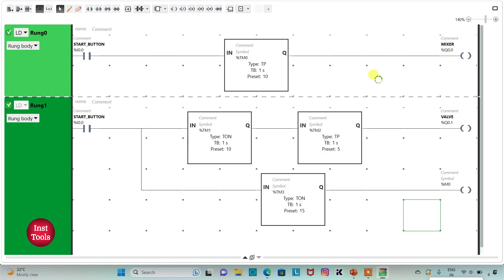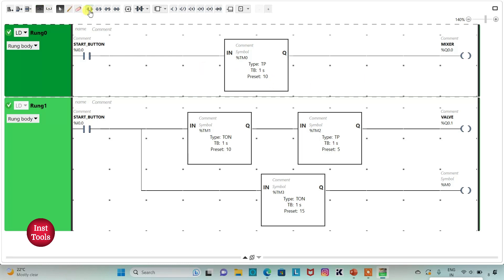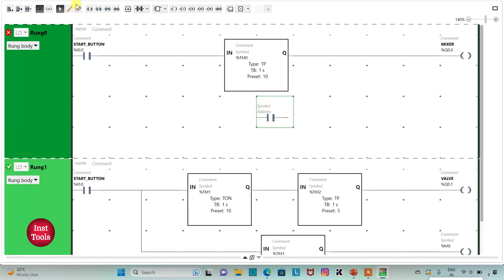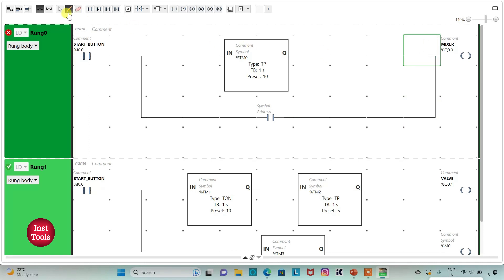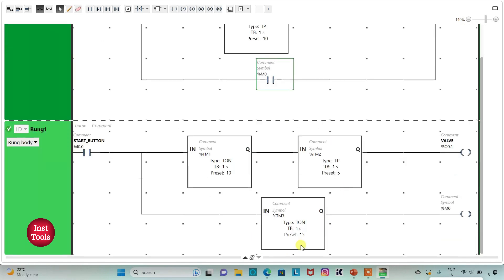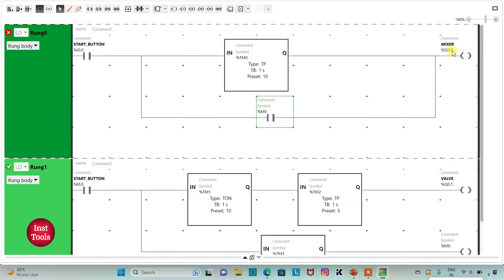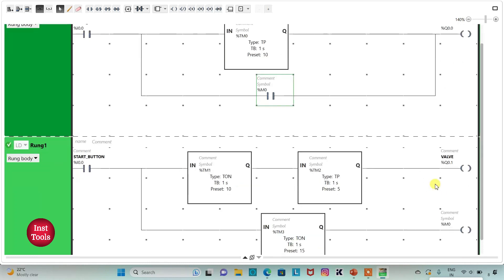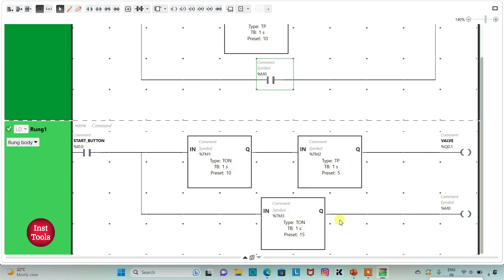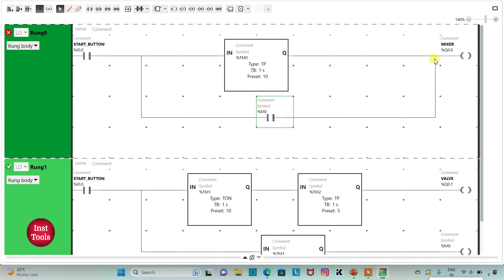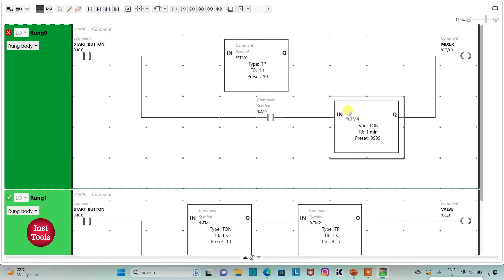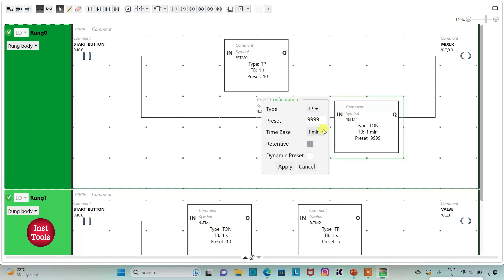In rung 0, I insert a normally open contact, connect it in parallel, and assign address M0 to it. After 15 seconds — when the mixer was on, then off, then the valve was on for 5 seconds and then off — the memory bit will be on. When memory bit M0 goes true, the mixer will turn on again. Since it should be on for 15 seconds, I insert one more functional block timer of type TP, set time base to 1 second and preset value to 15, then click Apply.